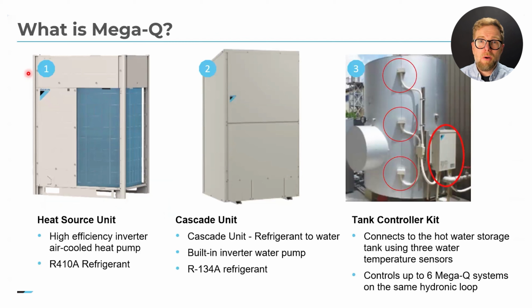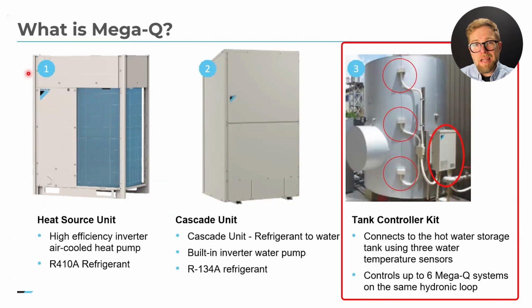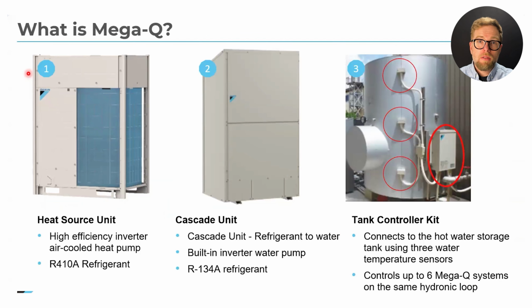Unlike a standard hot water setup, the MegaQ uses 3 different sensors inside the storage tank, each one reading a different layer of water that lets the system precisely control how much heating is needed at the top, middle, and the bottom of the tank. The result? Fewer spikes or drops in hot water temperature and less wasted energy heating water when you don't have to.